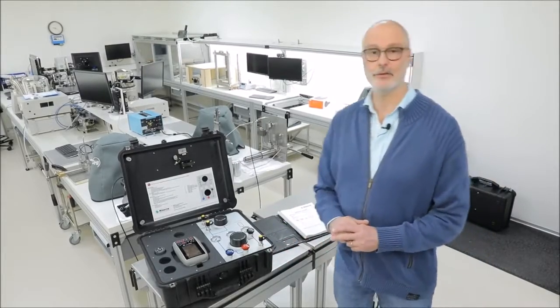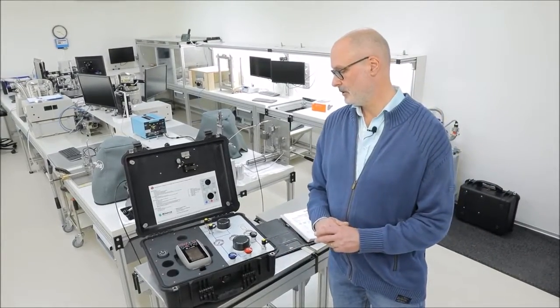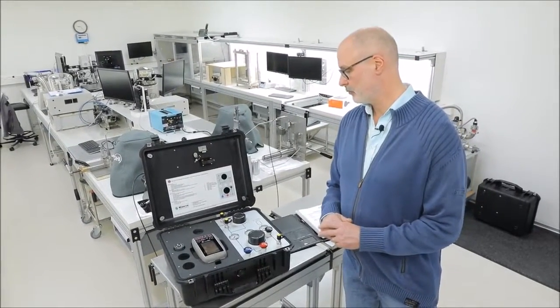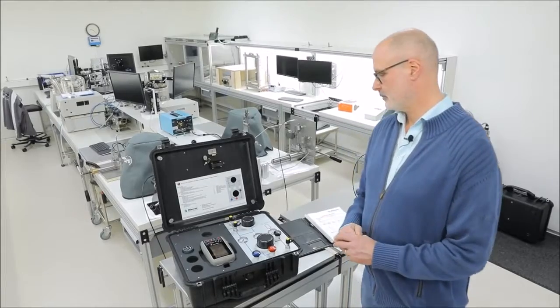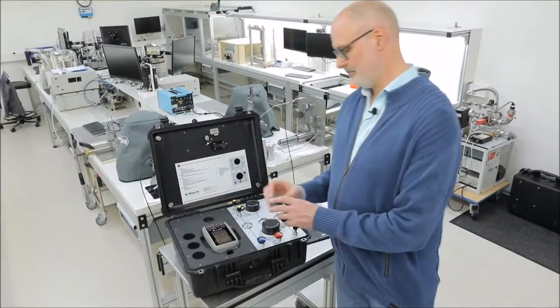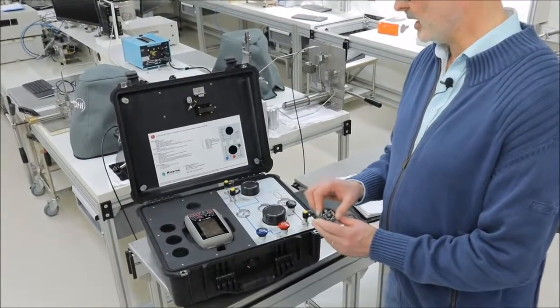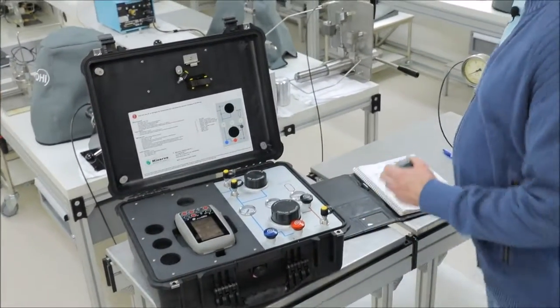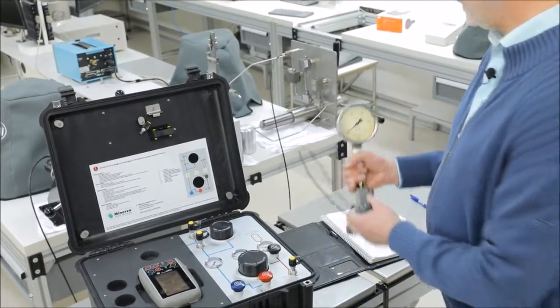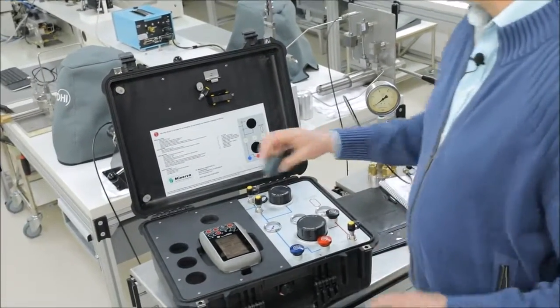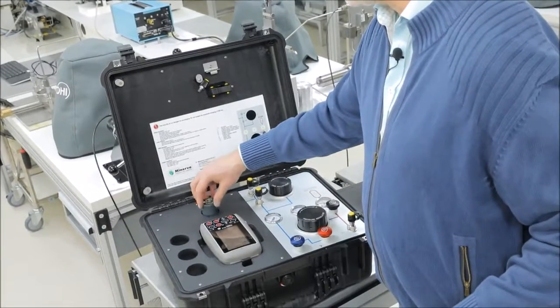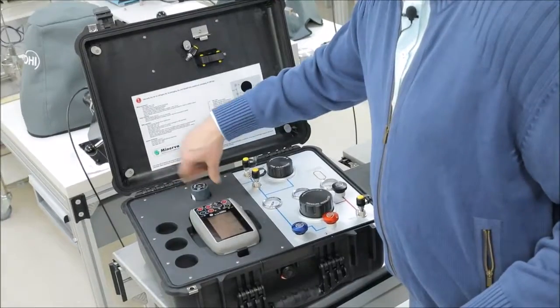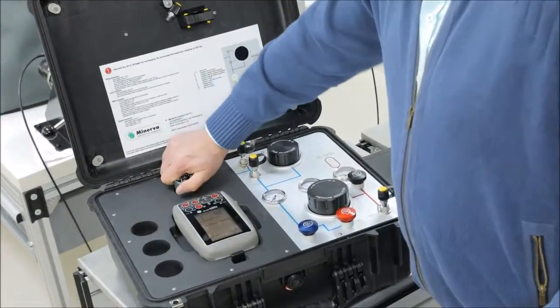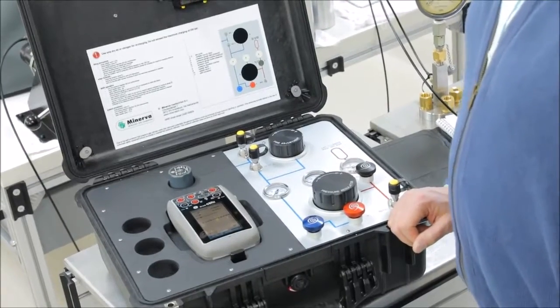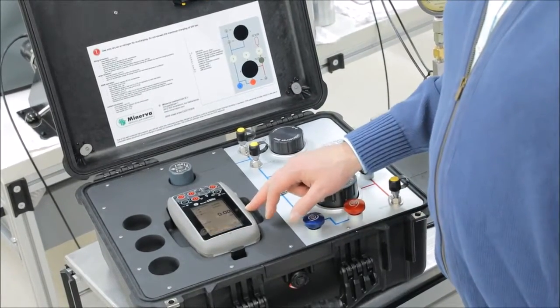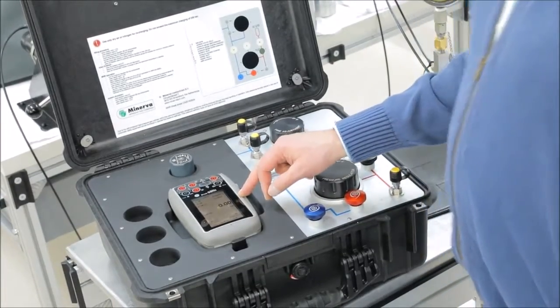Now I'm ready to demonstrate to you the advantages of our Minerva portable high pressure case by performing a real calibration. For this calibration we're going to use a PM620 pressure module, in this case it's a 100 bar version, to calibrate a 25 bar analog gauge. First we're going to connect my pressure module. Screw it in all the way, hand tight, and it will be automatically recognized by the DPI 620. It gives a nice 0.00 bar.